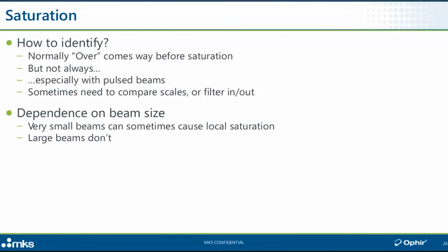Sometimes you'll hear theories or suggestions or concerns about a beam with a given power, if it's small, causing maybe local saturation on a detector, even if it's not a power level that should be saturating the detector. In a regular single element standard, semiconductor photodiode, that doesn't actually happen.